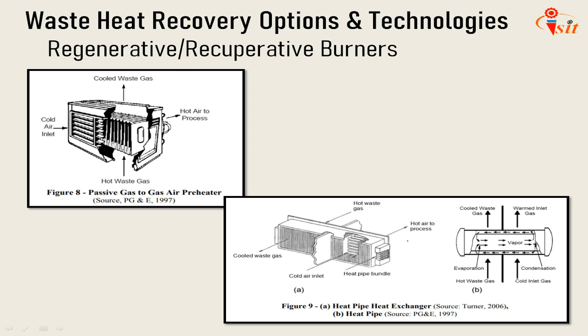Self-regenerative burners pass exhaust gases through the burner body into a refractory media case and operate in pairs, similar in manner to a regenerative furnace. Typically, recuperative burner systems have less heat exchange area and regenerative burner systems lower mass than standalone units. Hence, their energy recovery is lower, but their lower cost and ease of retrofitting make them an attractive option for energy recovery.